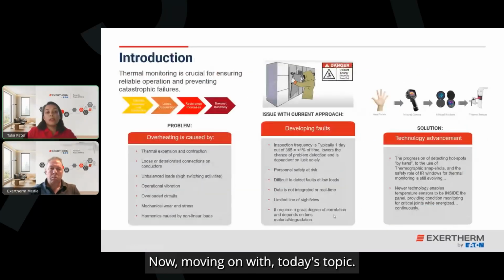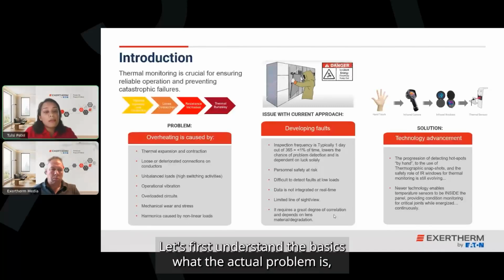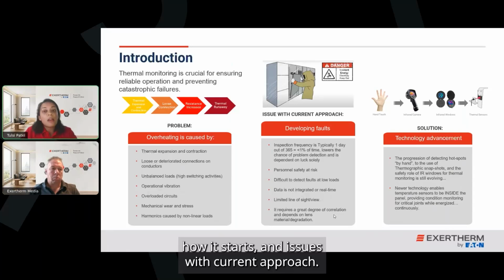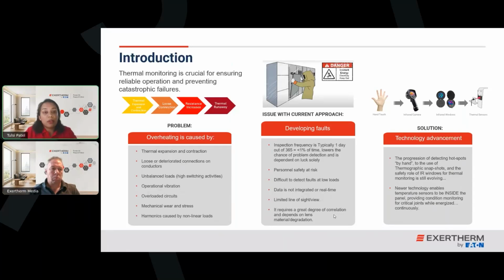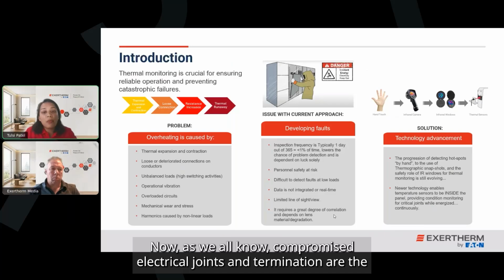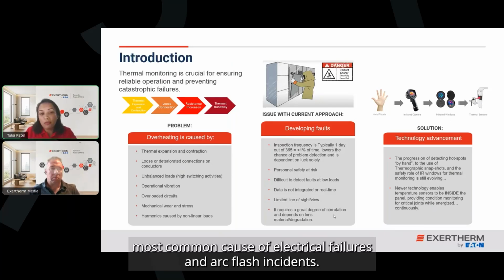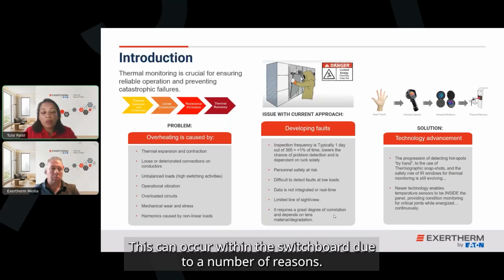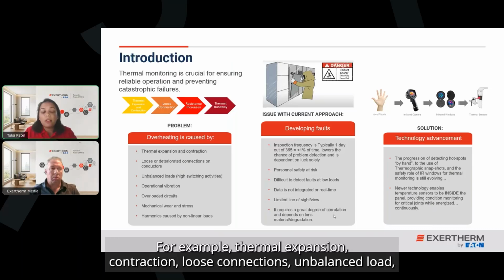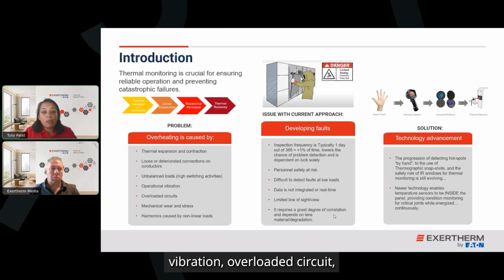Now, moving on with today's topic, let's first understand the basics: what the actual problem is, how it starts, and the issues with current approach. Now, as we all know, compromised electrical joints and terminations are the most common cause of electrical failures and arc flash incidents. This can occur within the switchboard due to a number of reasons, for example, thermal expansion, contraction, loose connections, unbalanced load, vibration, overloaded circuit, mechanical wear and stress, and harmonics.